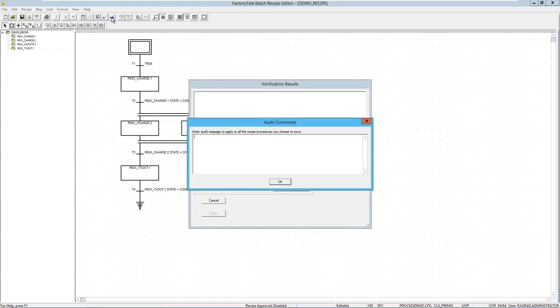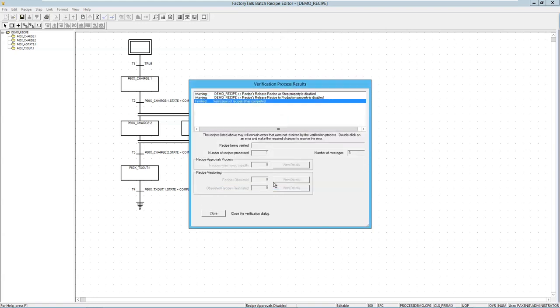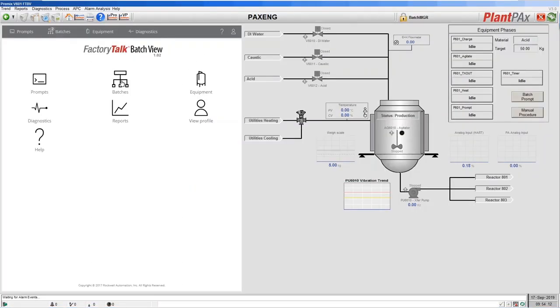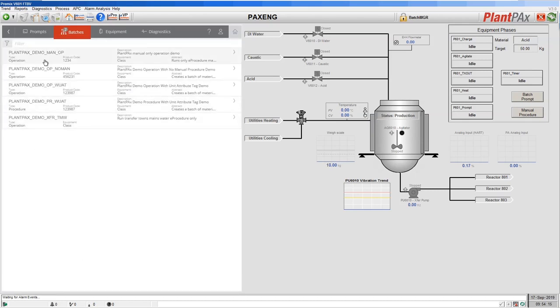As soon as we validate, we're asked to provide comments. Everything you do in the recipe editor goes into an audit trail. We can put in 'initial recipe validation' and then we're asked for audit comments for the save — 'initial save.' We've validated and verified the SFC and we have some warnings. Those warnings are telling us that the recipe is not released, so it cannot actually be run by any operator on the system. To show that, if we go back to our FactoryTalk View interface and click on our batches and say we want to add a recipe, we do not see demo recipe in the list. That recipe is not released — it's not available for someone to select.